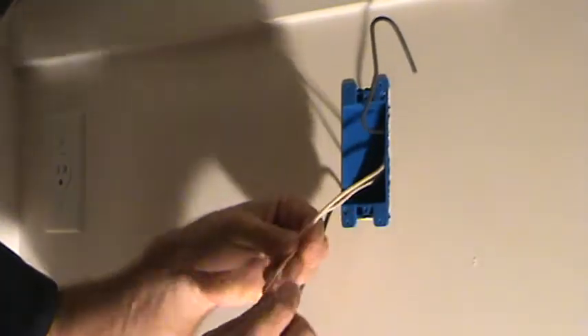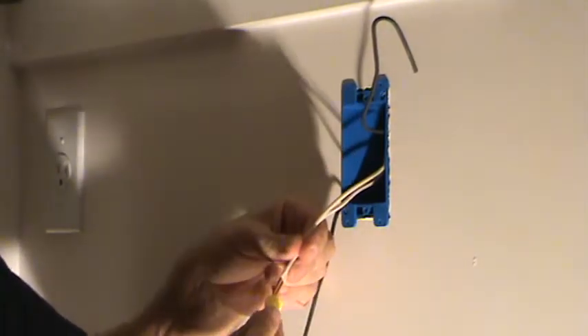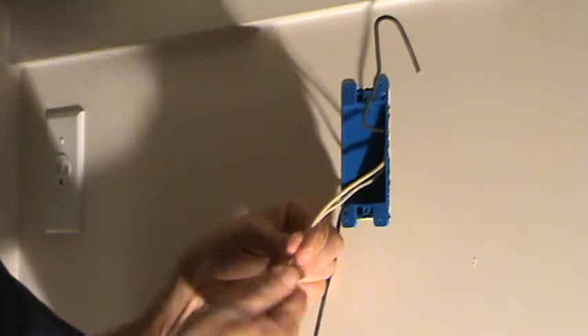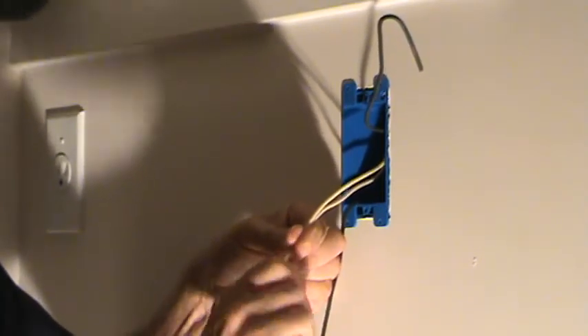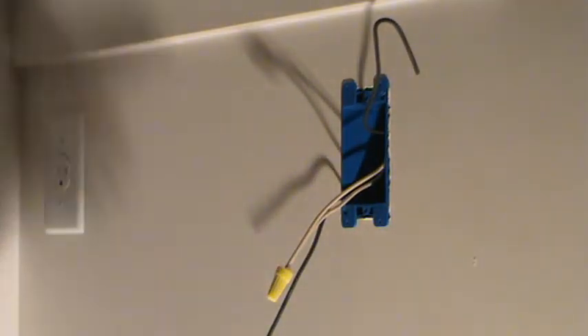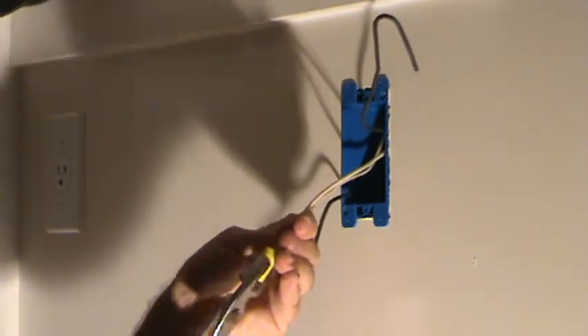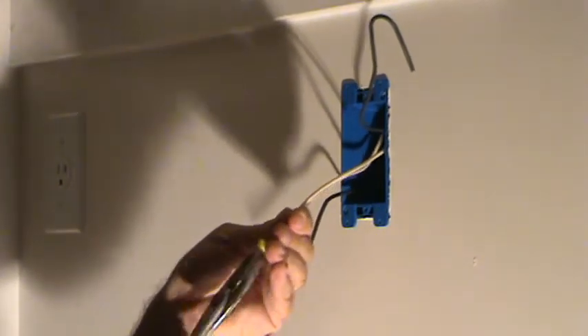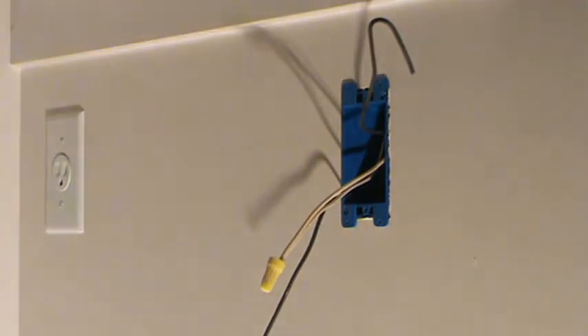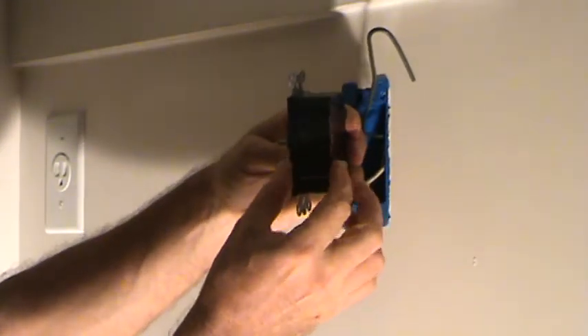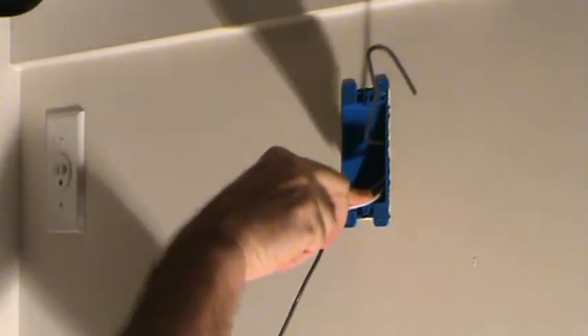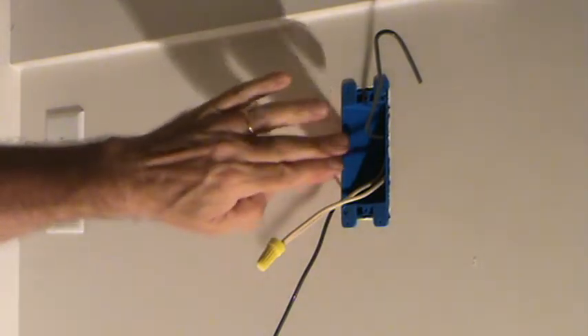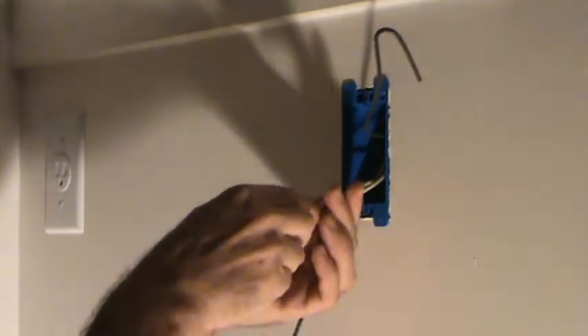Take another wire nut, a yellow. I don't need reds because the yellows are smaller and it fits everything back in the box. If you didn't have a yellow, could you use a red? Yeah, you could. I'm just trying to gain any little bit of an edge inside this box that I can, because this timer is pretty thick. It's got a deep body. See how thick that is? I've got to shove that all the way in there without hitting any of these wires. As I was telling you, they have deeper cut-in boxes. I could have used a deeper cut-in box. Then I wouldn't have to be so careful.